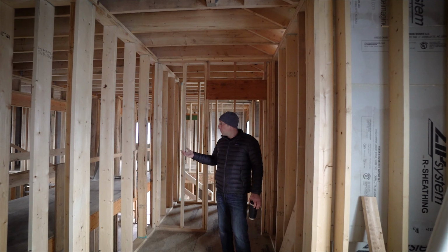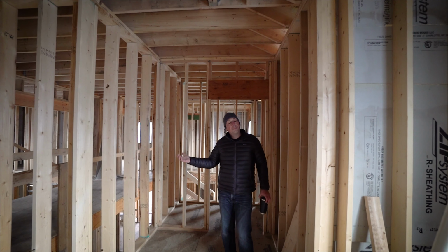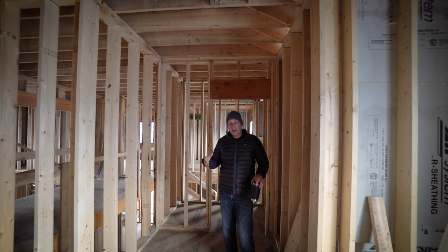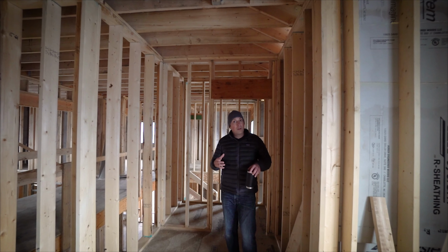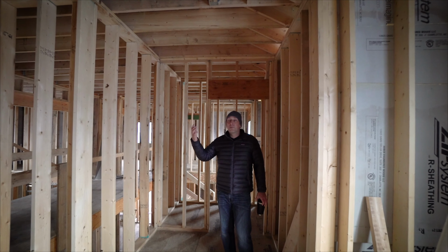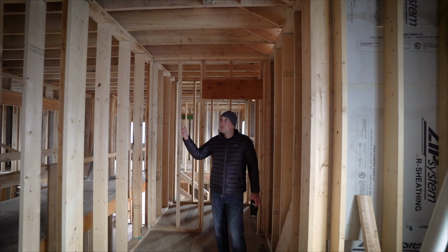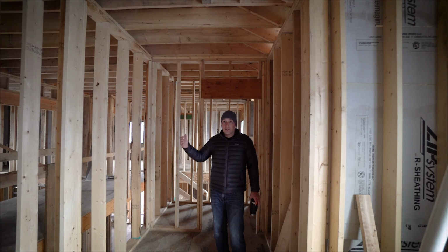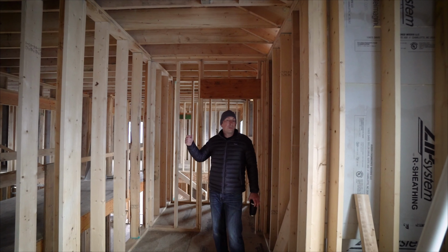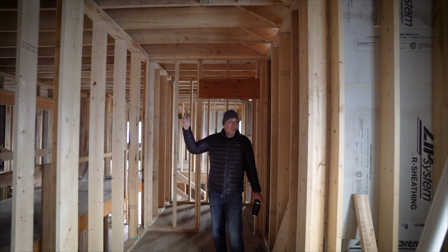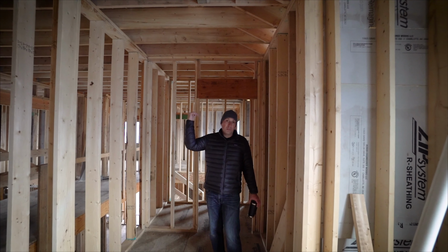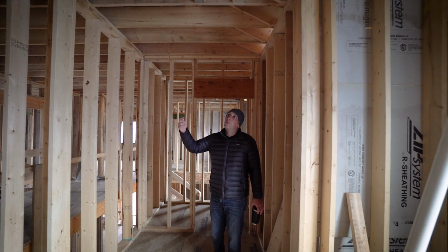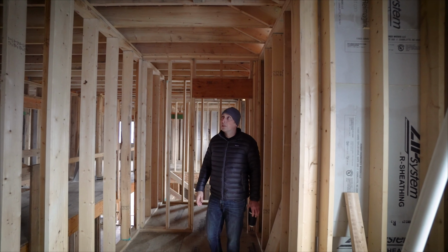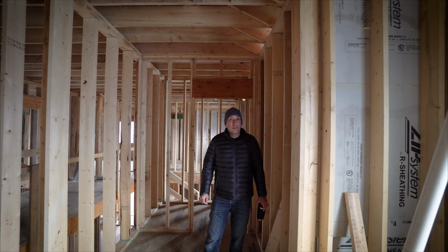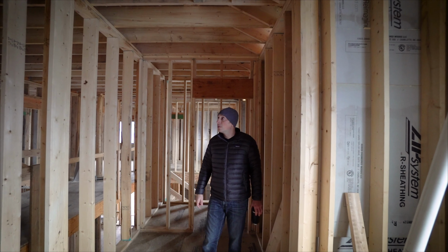We don't have any here to show you, but we'll show it on the next video -- you have to protect your ductwork. In the Midwest, we have vented attic space, so if it's 20 below zero outside, your attic is freezing cold. If you're running your heat through ductwork in those freezing temperatures, number one, it's going to be ice cold by the time it gets to the room, and number two, you're going to have a lot of condensation issues inside of it. So you've got to make sure your ductwork's insulated when it's running in unconditioned space.